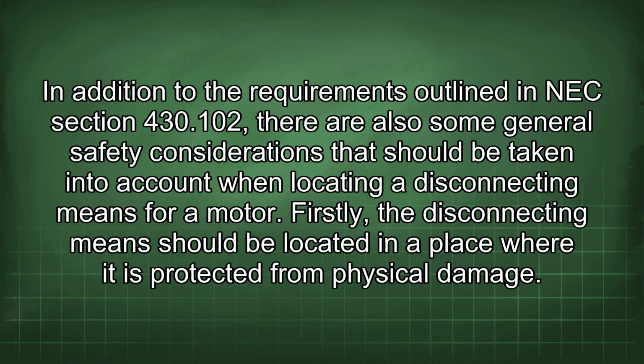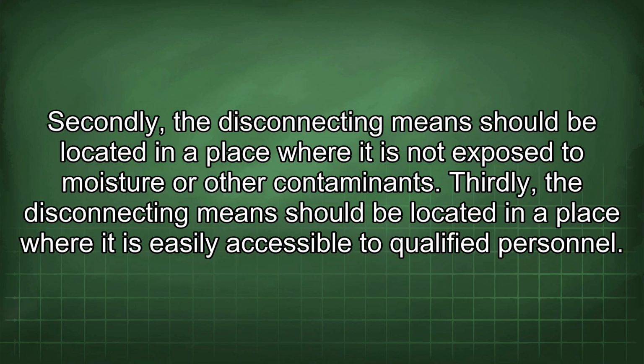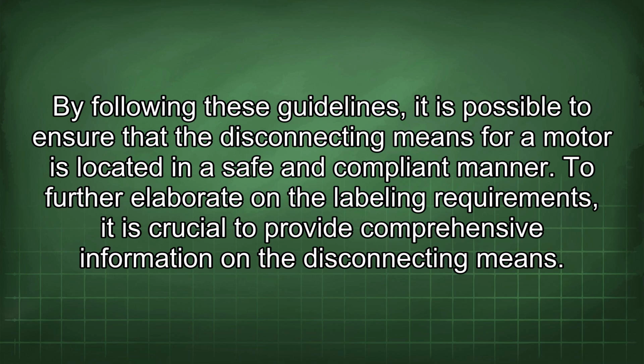In addition to the requirements outlined in NEC Section 430.102, there are also some general safety considerations that should be taken into account when locating a disconnecting means for a motor. Firstly, the disconnecting means should be located in a place where it is protected from physical damage. Secondly, it should be located where it is not exposed to moisture or other contaminants. Thirdly, it should be located where it is easily accessible to qualified personnel. By following these guidelines, it is possible to ensure that the disconnecting means for a motor is located in a safe and compliant manner.